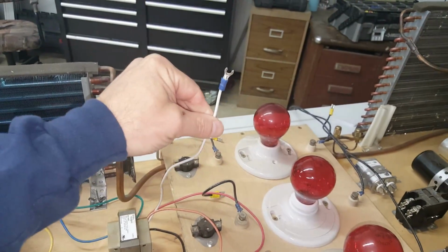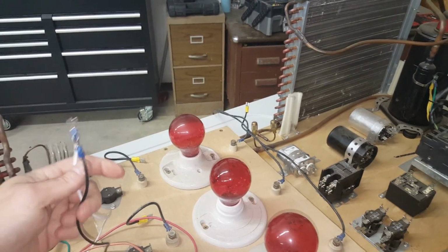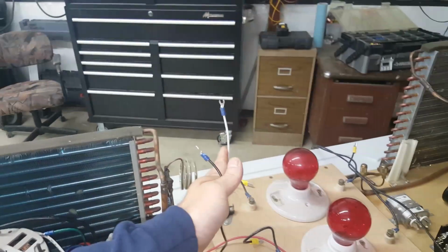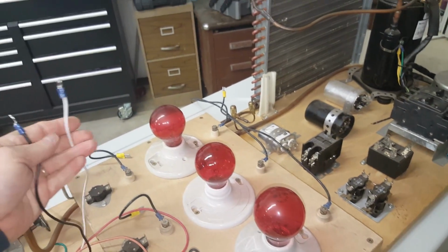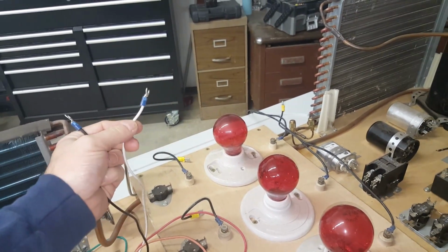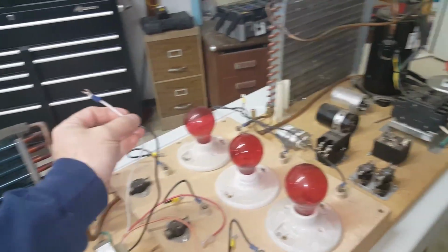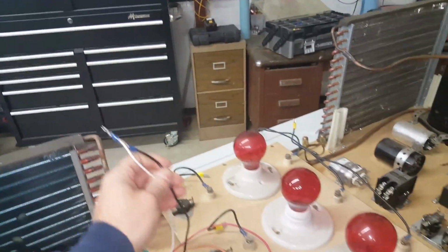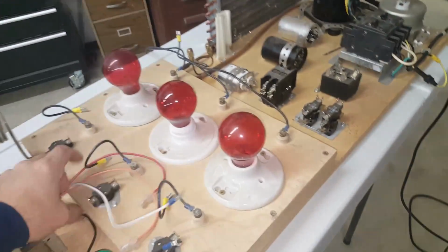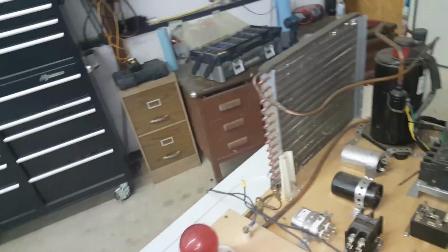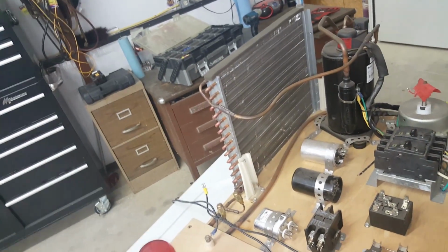Now, again, we're simulating the 240 volts, so that's why you see the connector on the 120 volt leg. So we're actually going to be using the common leg for the 120 hot, and the white wire will be our 120 volt hot, since this is in all reality 120 volts. But just remember, we're simulating it as 240 volts. In a real system, you would be hooking up the orange wire with the black wire. The other wires have to be capped off because they will feed electricity, and it will short out on the case or get you.